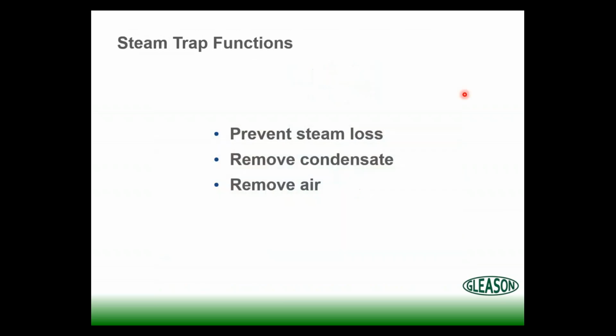So, steam trap functions. We want the traps to prevent steam loss, because steam is very expensive, so we want to keep that in the system. We want to remove condensate. Of course, as that steam gives up that massive amount of energy it carries, it condenses. We want that out of the system immediately as it forms. And lastly, we want to remove the air and other non-condensable gases from the system, because air is an insulator.